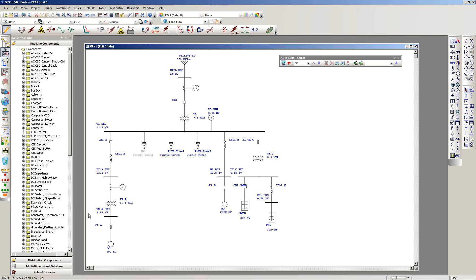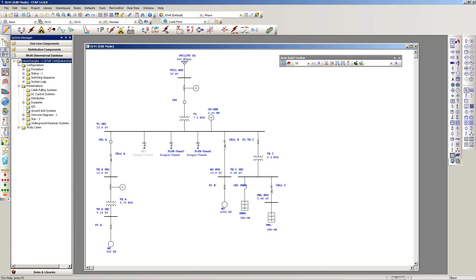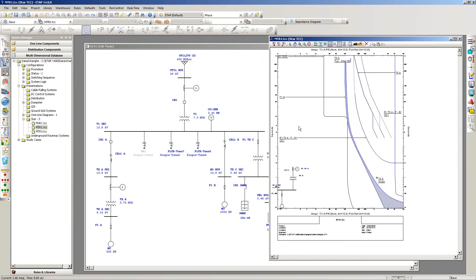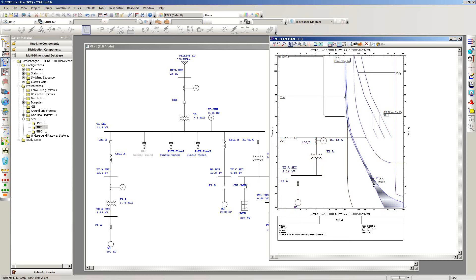The other item to cover is TCC import. For projects that already have TCCs created, ETAP 14 makes it very easy to bring them over. In the imported project, going to the multi-dimensional database on the left and expanding the STAR TCC folder, you can see three TCCs that were created originally. Opening the first TCC called 'Motor 1,' you can see the preview of that section of the model with the TCC at the bottom left corner, including the motor acceleration curve and all protective device and damage curves such as the transformer damage curve, automatically mapped over.